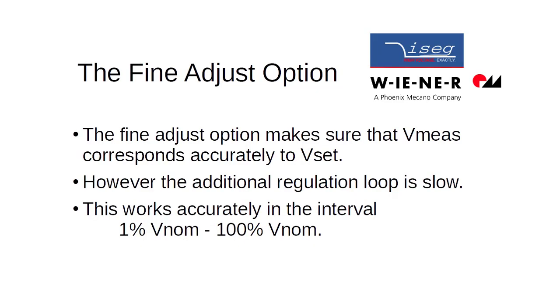Now we will take a look at the fine adjust option. The fine adjust option activates an additional regulation loop that makes sure that the measured voltage corresponds to the set voltage. This additional regulation is slow, especially at higher voltages. This is the reason why the option is not active by default. This option is guaranteed to work in the range of 1% to 100% of the nominal voltage.